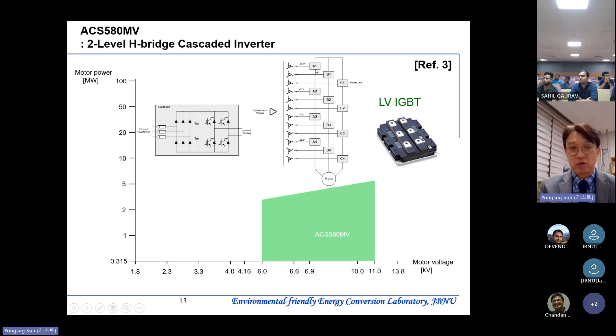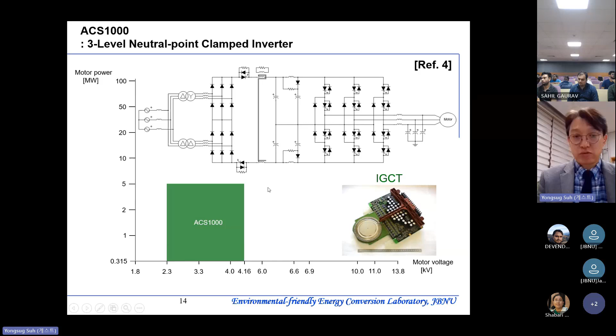Next one is ACS 1000. This covers relatively lower voltage than H-bridge but higher power, and this is a typical example of the IGCT case. The upstream is a diode rectifier, and this is the general 3-level neutral point clamped inverter case. This is the RCD snubber, unique to IGCT, and the common mode filter, and this is for shutting down IGCT for protection issues.